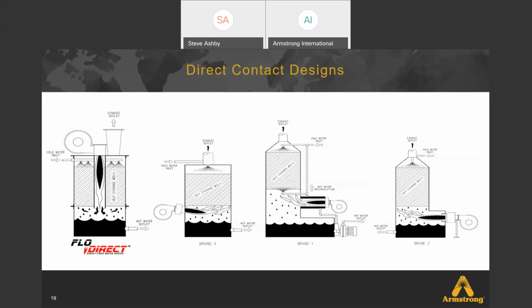So again, we're only heating with gas. So that gas comes down, comes vertically upward. There's Pall rings in a media in that center can that holds heat. And as the water sprinkles vertically downward, hot gases move vertically upward, and that's where your efficiency of near 100% heat transfer takes place. Pretty simple design.